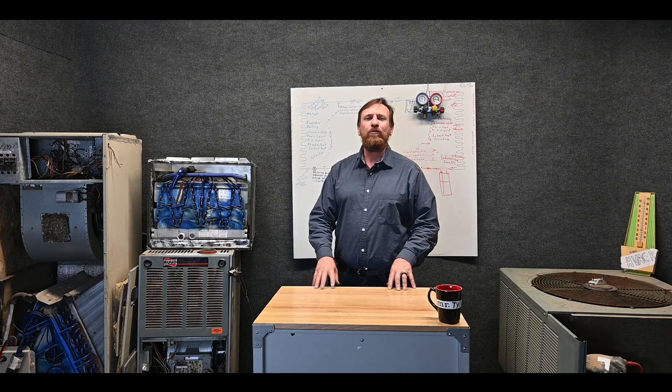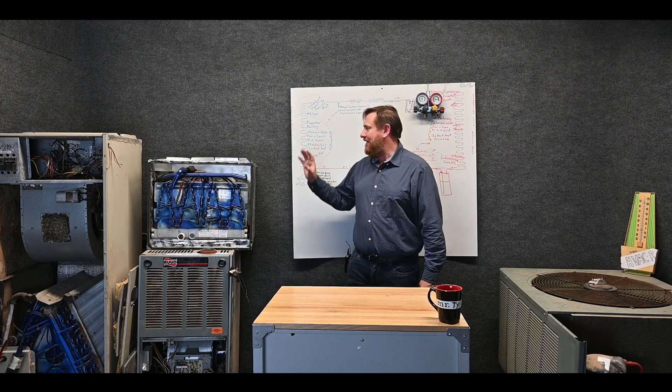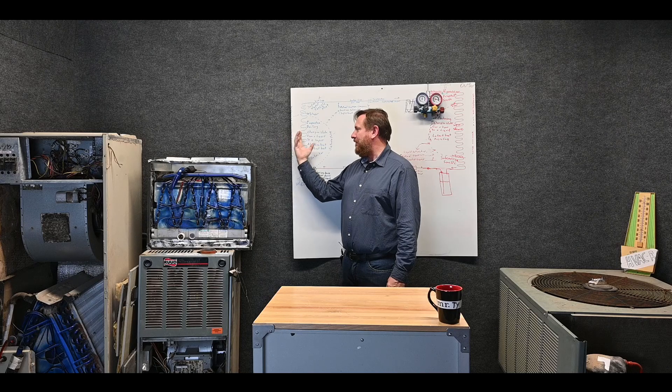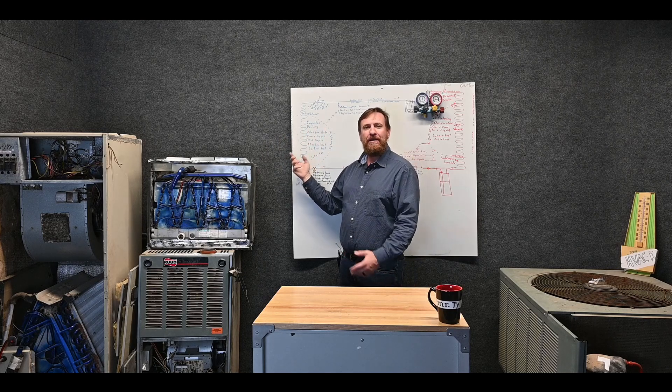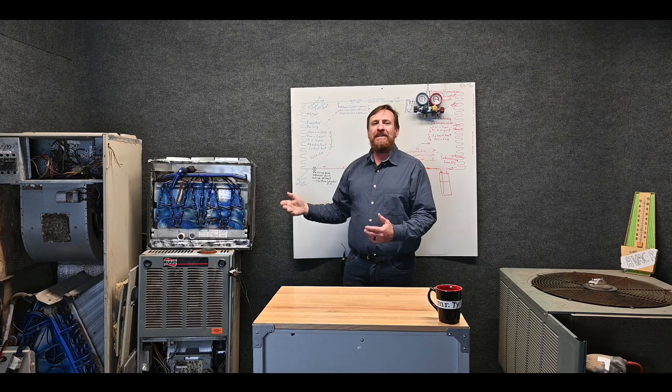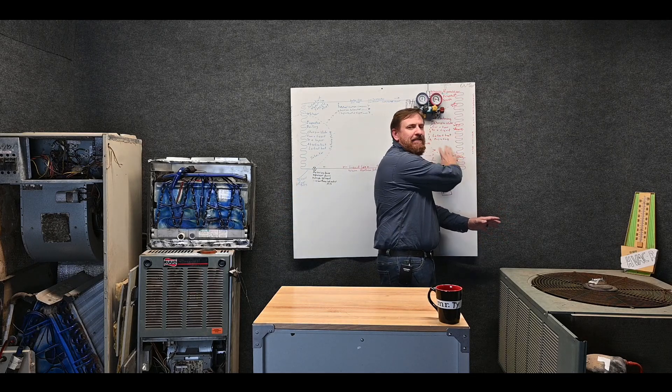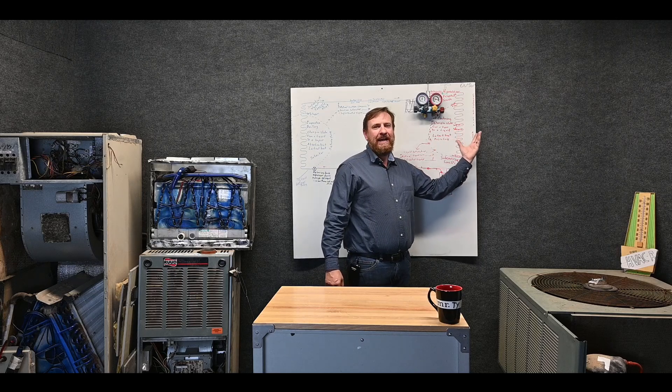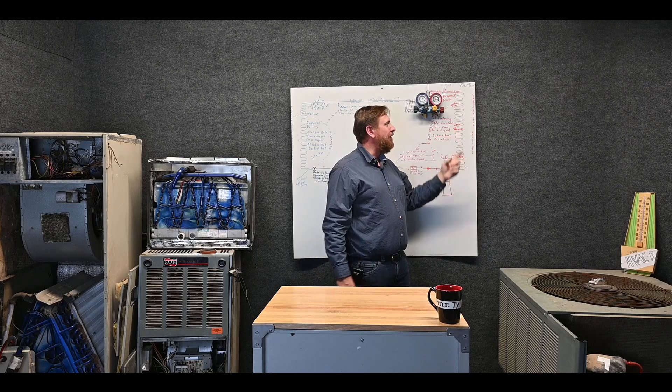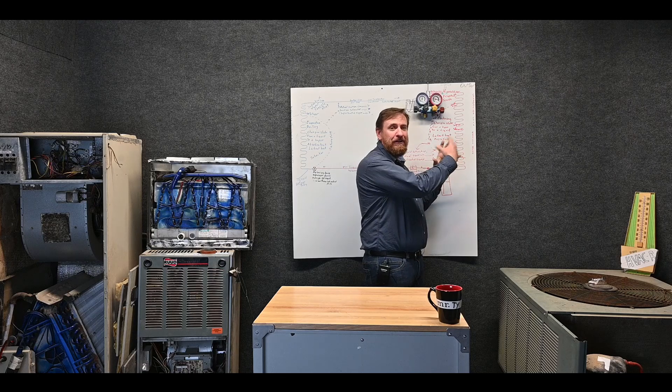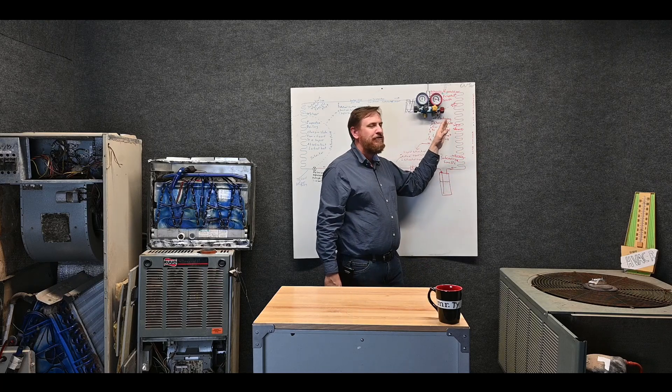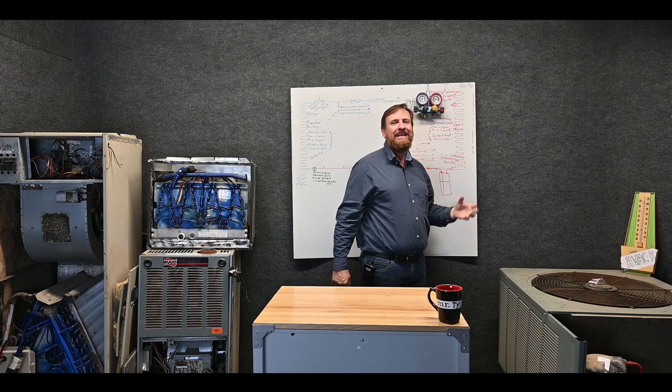Now let's go over what's happening. So let's roll through that scenario. We know that we have a dirty evaporator coil inside. We know that we don't have enough heat coming across it. So therefore my temperature around this evaporator coil is dropping, which means my suction pressure also drops, which means my saturated or boiling temperature is also dropping down. But on the counter side of that, my outdoor unit over here is completely clogged up as well. It's also blocking airflow and heat transfer. So as that air is coming through here, it's not transferring heat very well. To make up for it, we have higher pressure because that heat's building up around it. So the temperature goes up, the pressure on the outside unit goes up, and now we have a bigger temperature difference between the refrigerant and the air. And we're able to force that heat to leave the refrigerant.